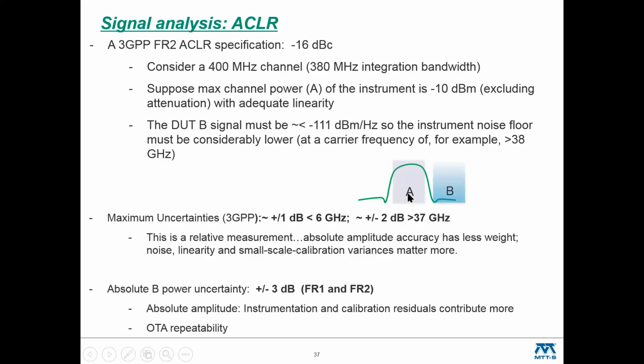I can measure these at the same time. So there'll be some noise and linearity kinds of contributors to uncertainty, and we do have to calibrate for the receiver's slope over this roughly 800 megahertz range. But that seems not too bad. But there's another specification for absolute power in B over, I think it's a subset of this channel width, but there's an absolute power specification. They give an uncertainty allowed there of 3 dB, and this is of late last year. I'm not sure if this number has changed.